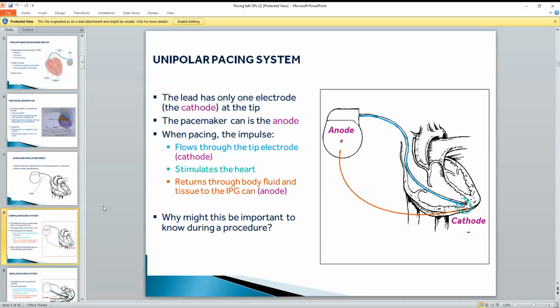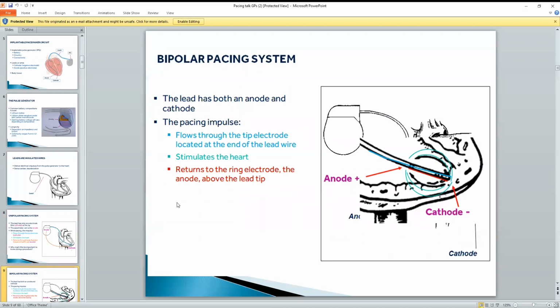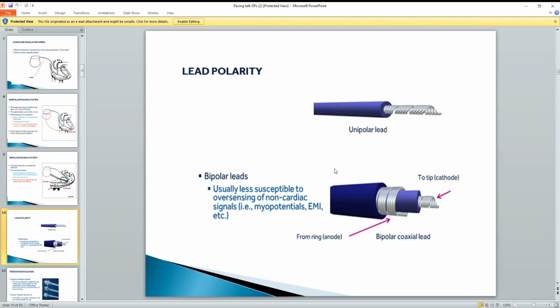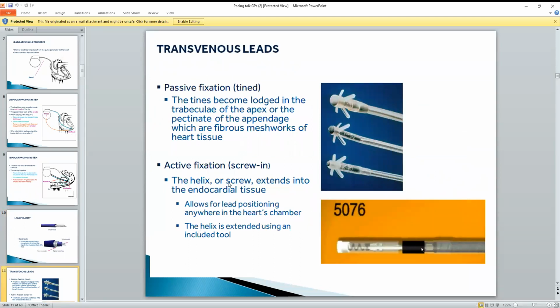You may come across the term unipolar pacing system. This is a sort of old-fashioned system, made up of the wires, the battery, as well as the body tissue. The newer devices are bipolar, so they are localized to the tip of the pacemaker. So there are two different types of leads you might come across: unipolar and bipolar. The leads are transvenous, so they are within the venous system of the heart. There are two types of leads that are commonly used, passive and active. Does anyone know what the advantages and disadvantages might be of these leads at all?